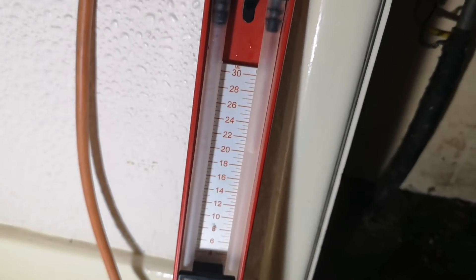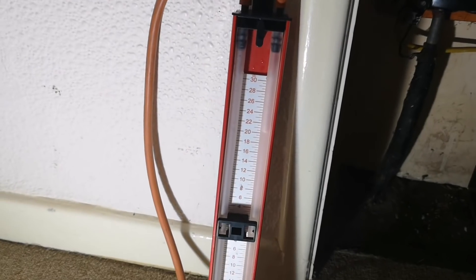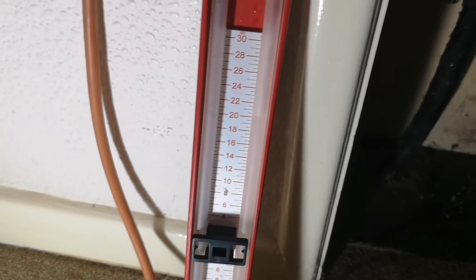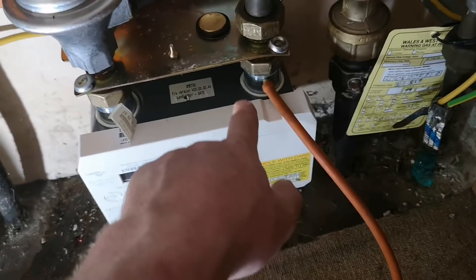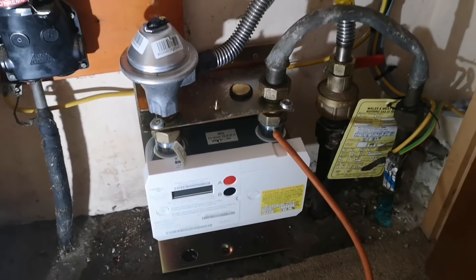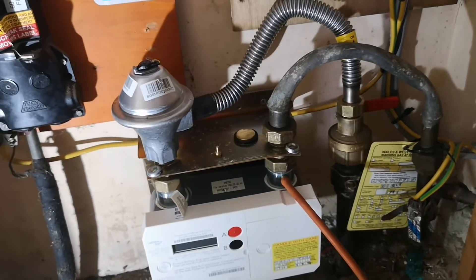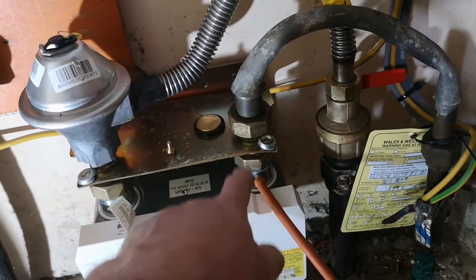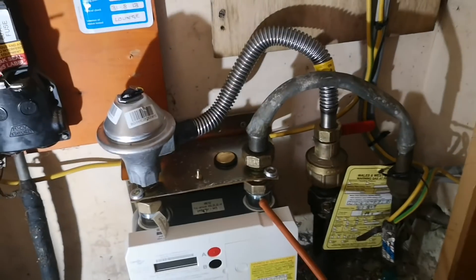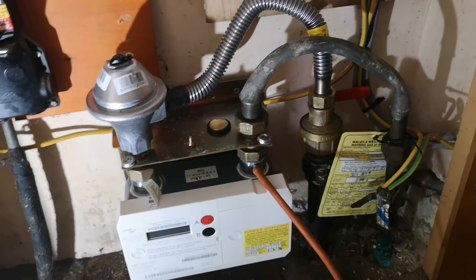Now we've pulled a bit of gas through at the boiler, we'll put another quick test on - one minute stabilization, two minute test. Just completed my second test after pulling a bit of gas through the boiler and checking the connections were actually turned on, just to make sure there was no second isolation cap in there because it's really tight and I can't get it off without putting a massive amount of force through it. No gas leak - two tests now and they both come back rock solid.